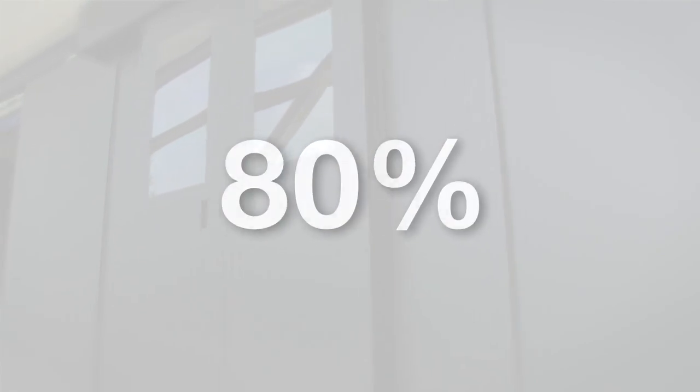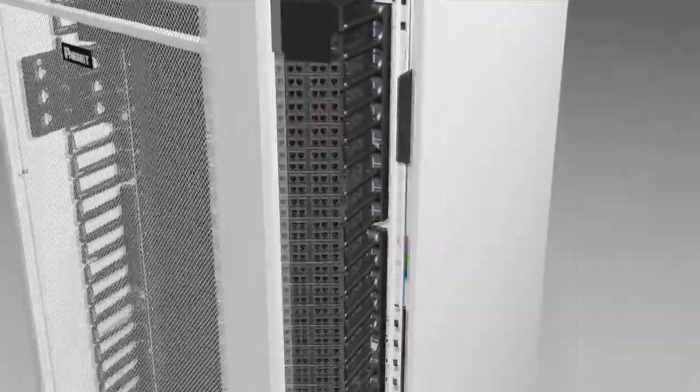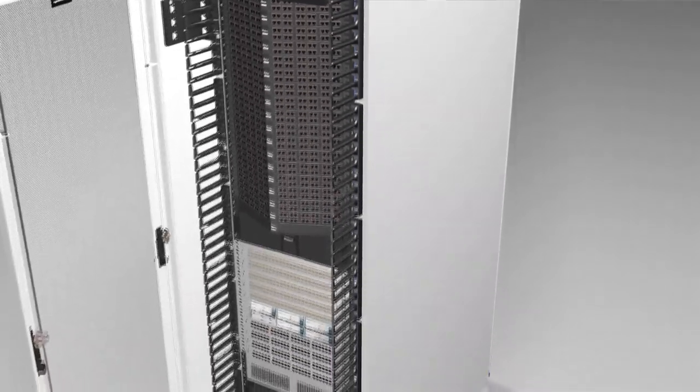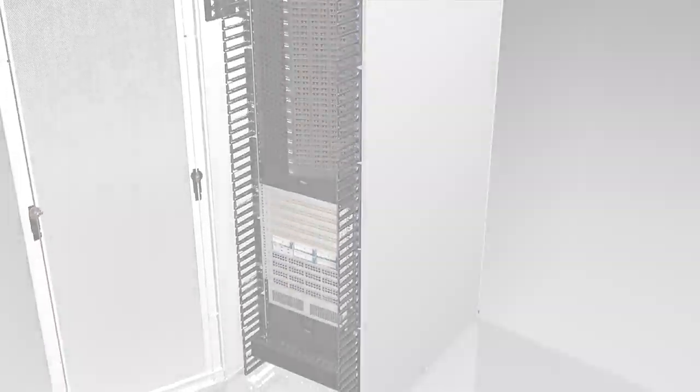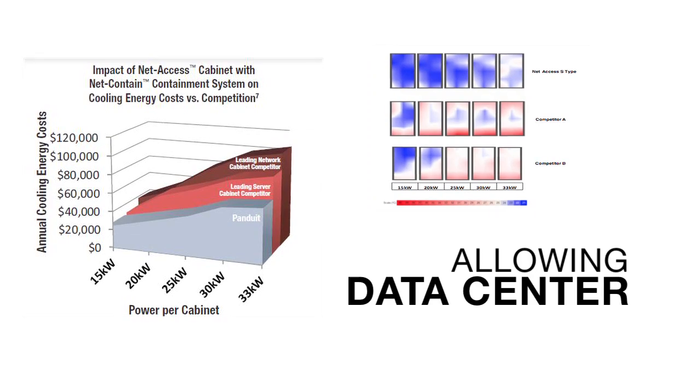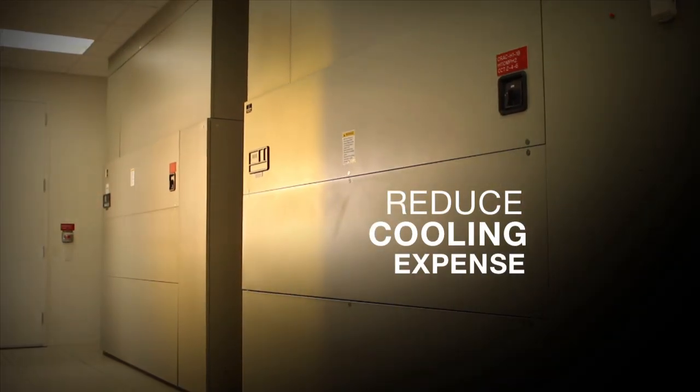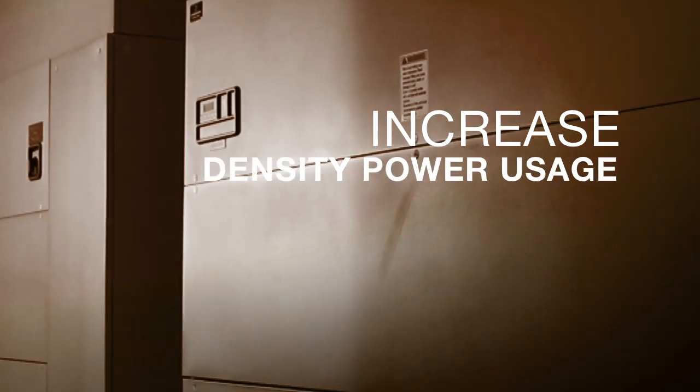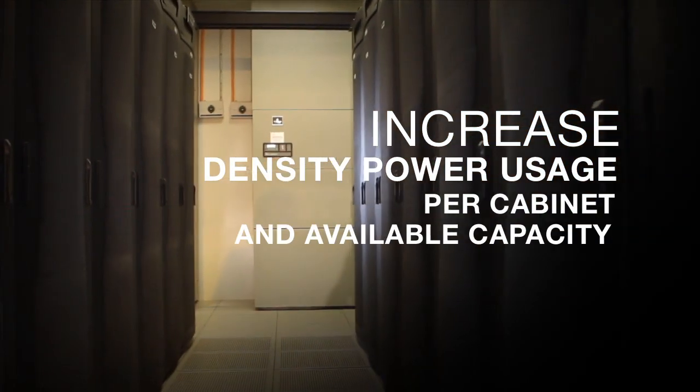Panduit Net Access Cabinets reduce the air leakage that's typically found in competitive cabinets by as much as 80%. By preventing hot air recirculation, a more consistent inlet temperature gradient can be realized across the entire front of the cabinet, allowing the data center set point to be raised. This results in reduced cooling expense and an increase in both density power usage per cabinet and available capacity.